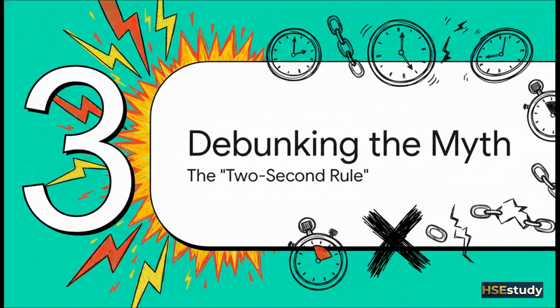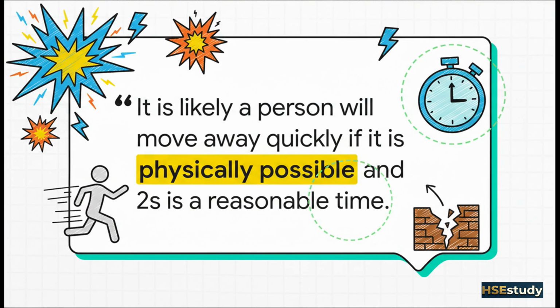So many engineers, so many electricians believe that an arc physically cannot last longer than 2 seconds, and that belief comes from a complete misunderstanding of the standard, a misunderstanding that has fatal consequences. Here it is, straight out of the IEEE 1584 standard, but you have to read it carefully. This isn't about the physics of an arc. It's an assumption about human behavior.